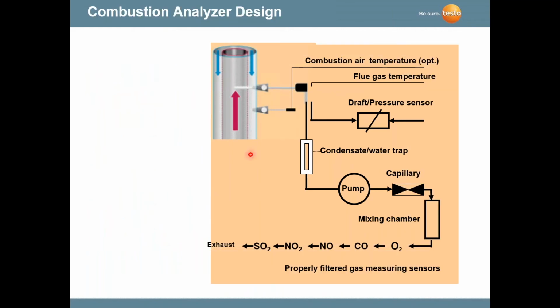Now, on a combustion analyzer, the probe and hose assembly could be several feet long. Your hose could be 7, 8, 10 feet long. Maybe you're using a hose extension. We can do that. The probe tube here is around 12 inches. Convert that to metric, but you're pulling a sample of flue gas from the stack gases through a probe assembly with a filter on it. Then it goes through a water trap. From the water trap, it goes internally into the instrument. And then the last place that the flue gas goes before it's exhausted out of the instrument is to the sensors. So it's important that we have a tight seal between the probe tube that's in the stack all the way to the internal plumbing of the instrument.